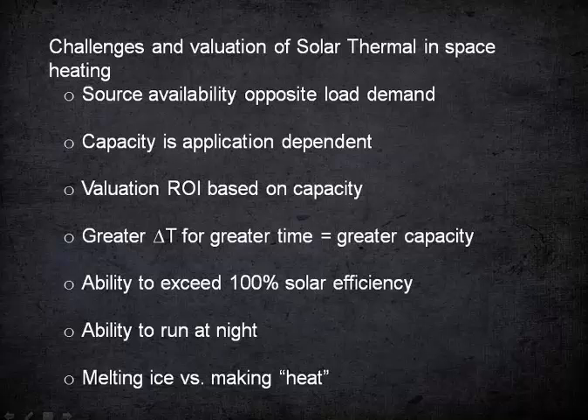In temperature direct-to-distribution solar thermal applications, which we believe makes up 100% of current industry thinking about how to apply a solar thermal collector, we'd challenge that perspective. Solar thermal directly to the load is certainly the most efficient, but it doesn't have the highest capacity. By putting it on the source side of a thermal battery and using a heat pump, you can get a lot more heat out of them.